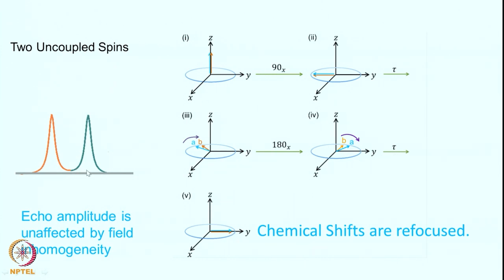These two spins considered could be separate independent spins, or they could be the same spin located in different portions of the sample due to magnetic field inhomogeneity. If the magnetic field is inhomogeneous, one portion of the sample sees one field, another portion sees another field, resulting in different precessional frequencies. As a result of the echo, they come back to the same position — we say the echo amplitude is unaffected by field inhomogeneity. This important concept will be used later for measuring transverse relaxation times.